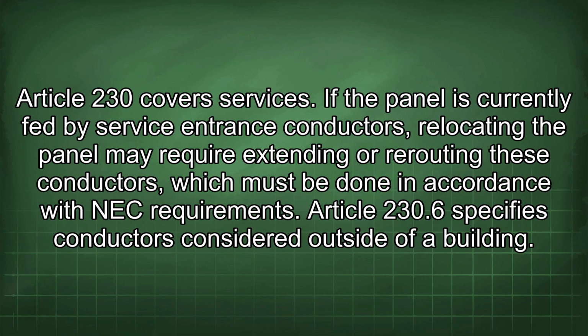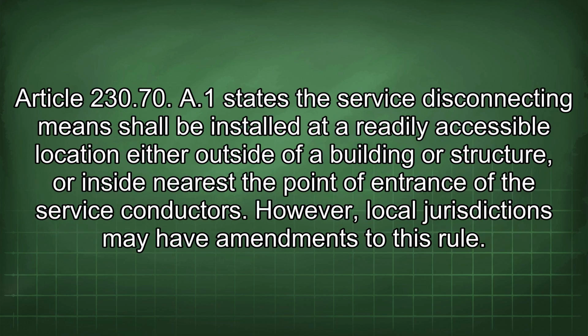Article 230.6 specifies conductors considered outside of a building. Article 230.70 A1 states the service disconnecting means shall be installed at a readily accessible location either outside of a building or structure, or inside nearest the point of entrance of the service conductors. However, local jurisdictions may have amendments to this rule.